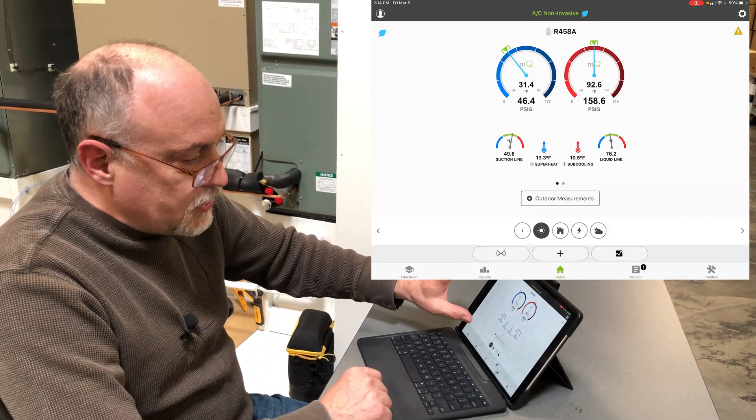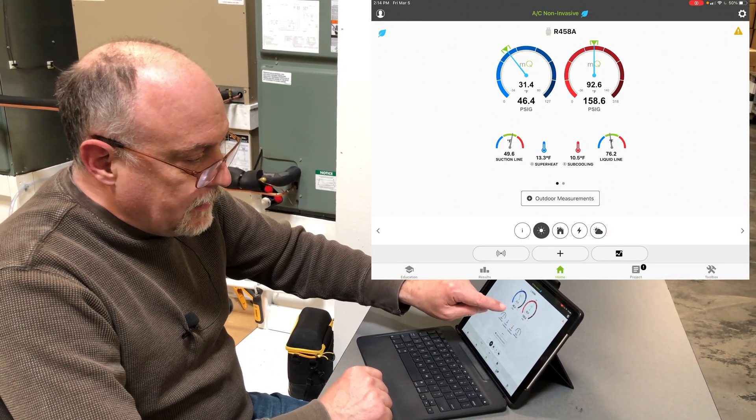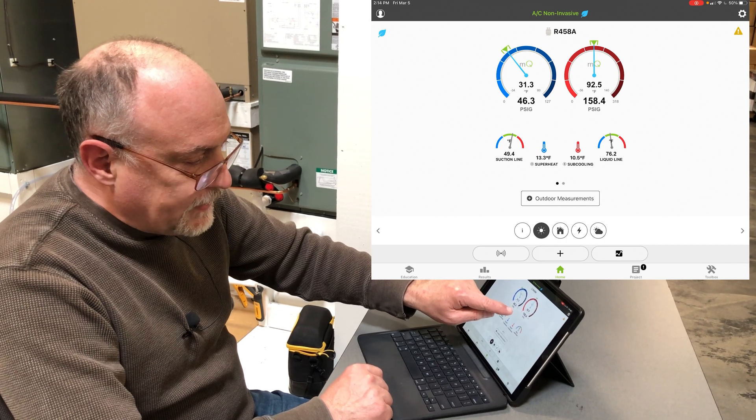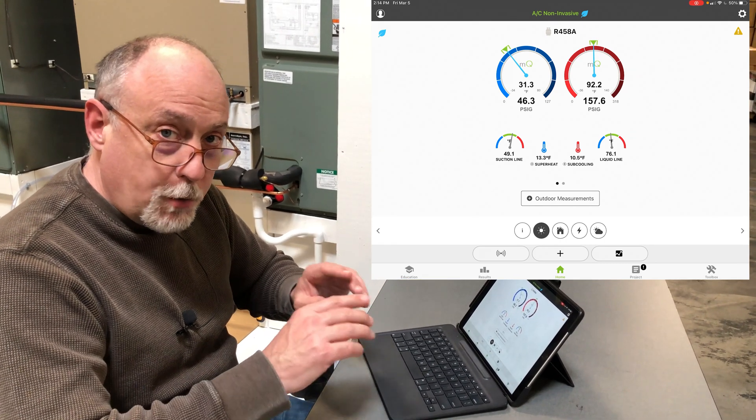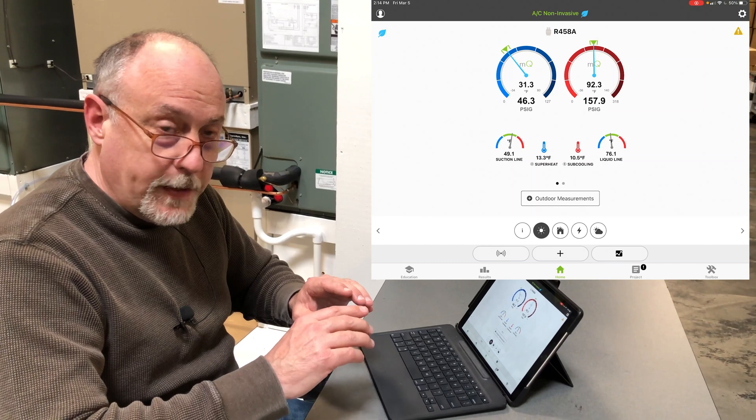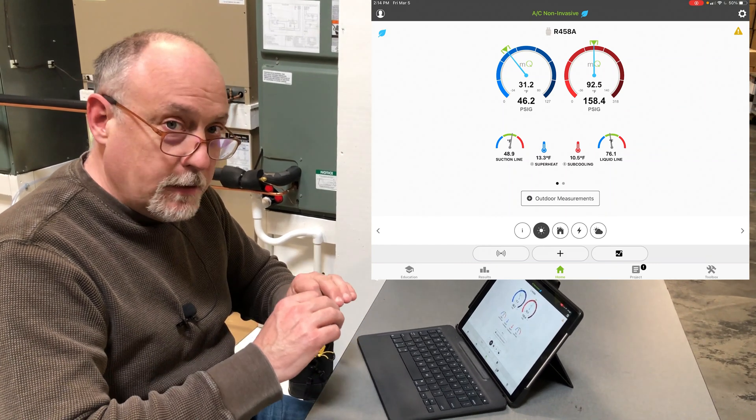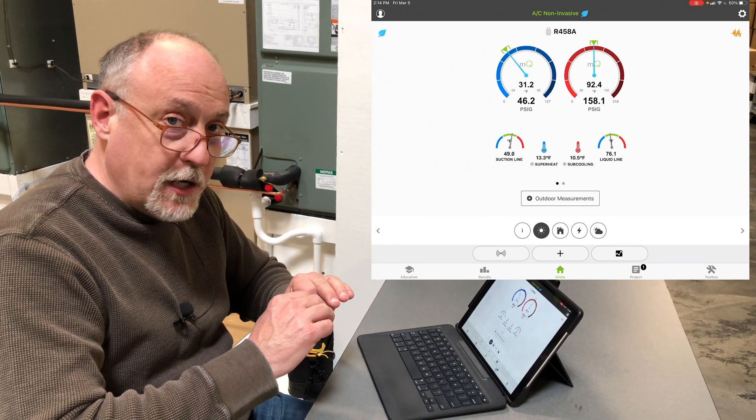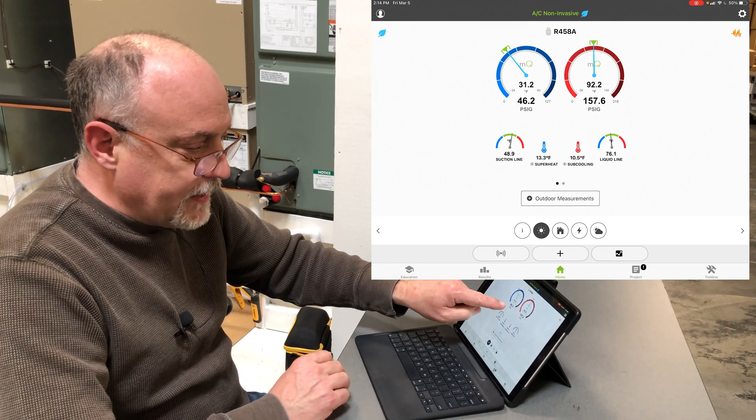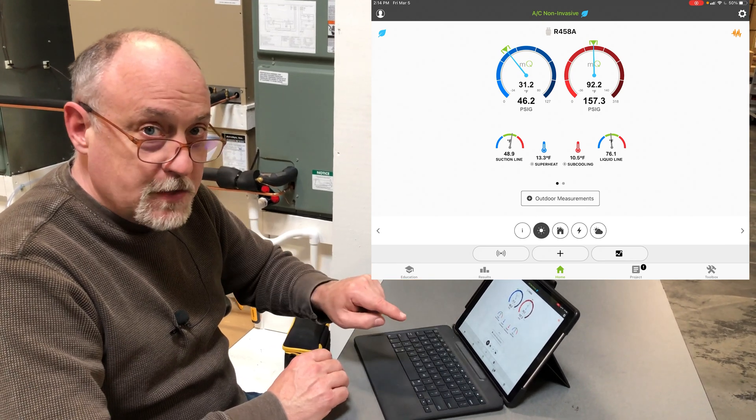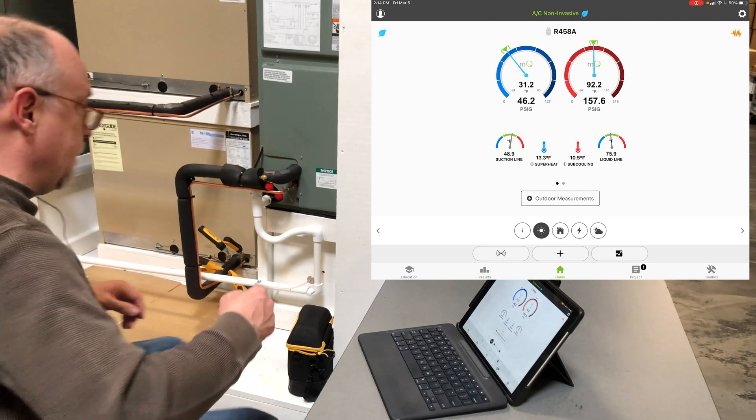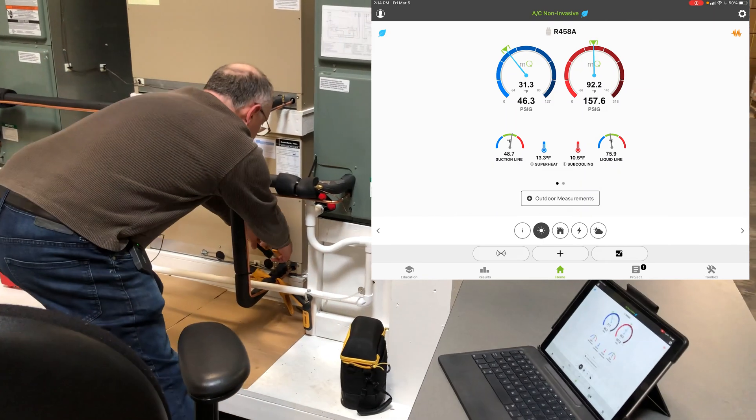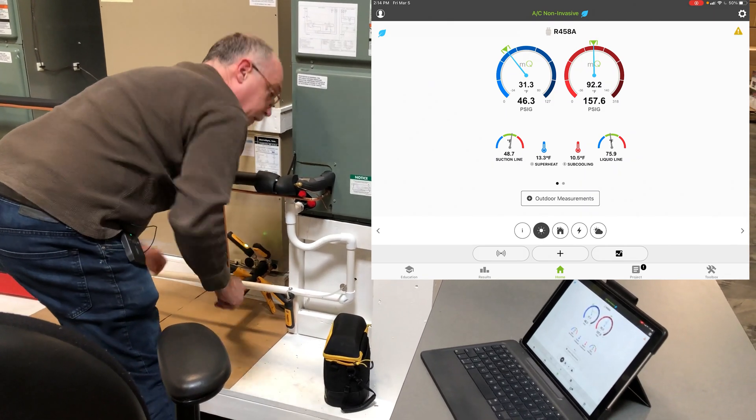To show you how accurate this is, you'll notice here it's 46 and 158. I'm going to turn on the probes now for MeasureQuick and show you how accurately MeasureQuick will calculate what the pressures should be. Right now it's saying they should be 46 and 157. When I turn it on, you'll see the actual pressures come in. We'll kick these on here and the needles will change color.